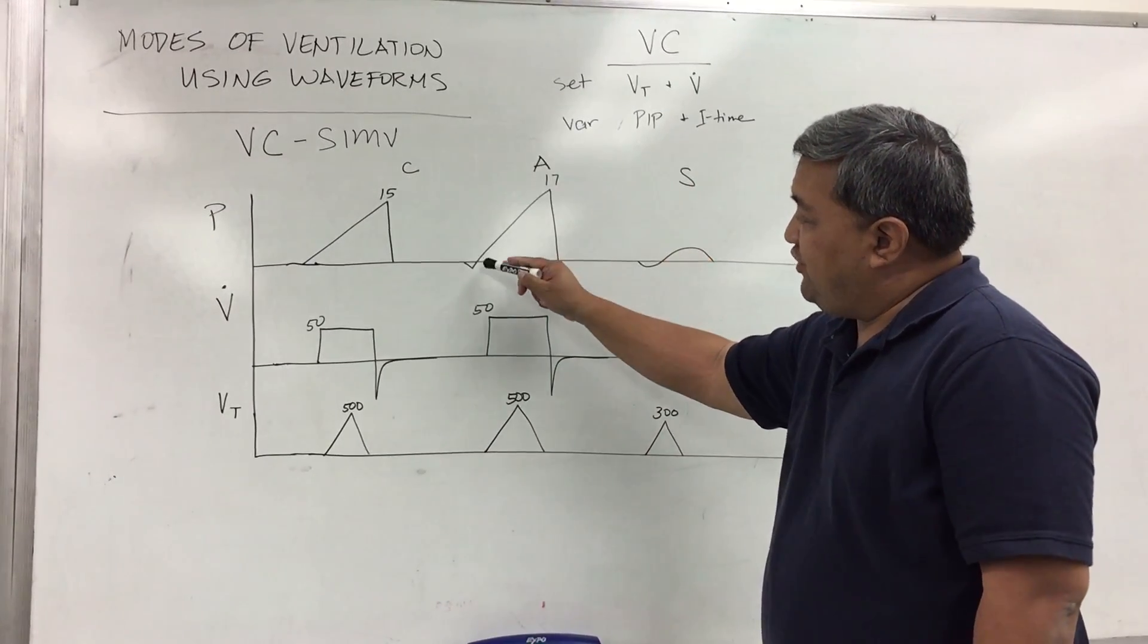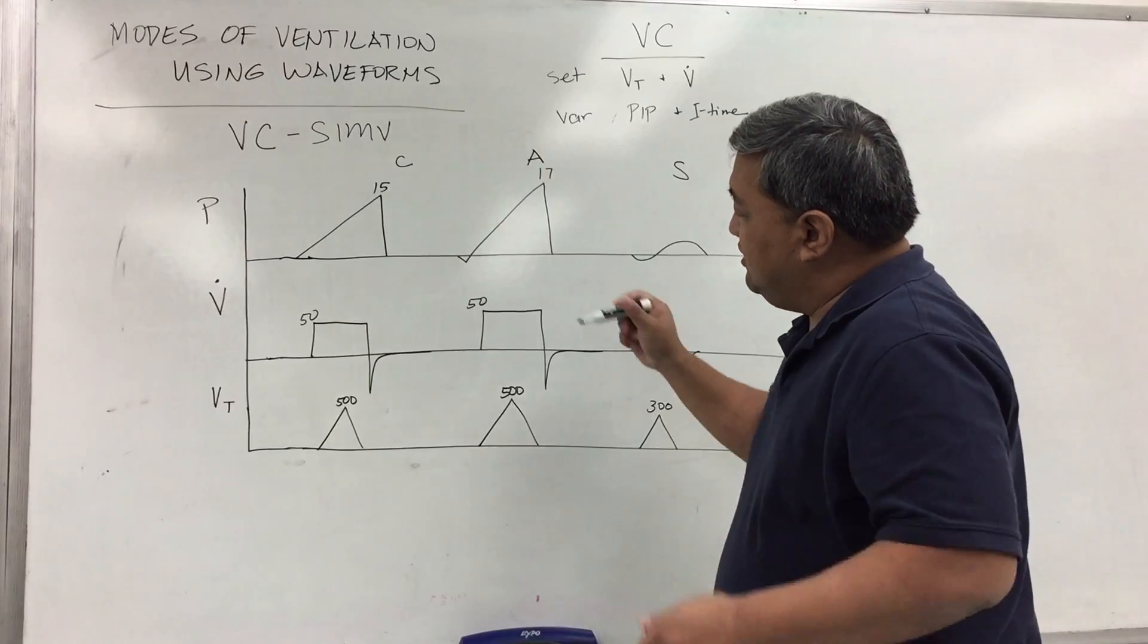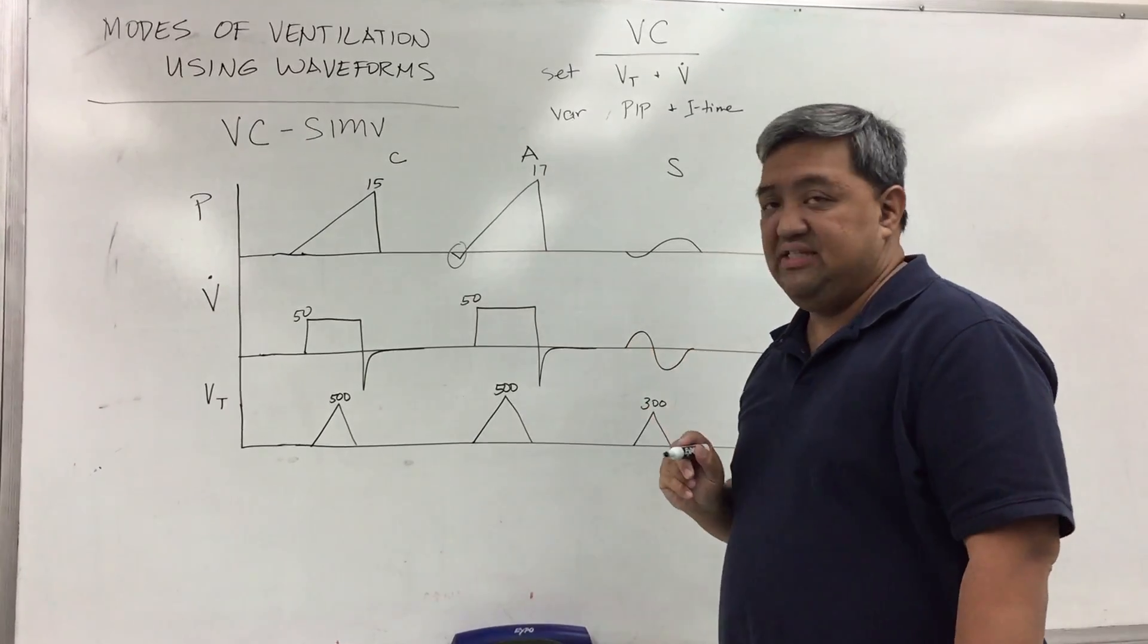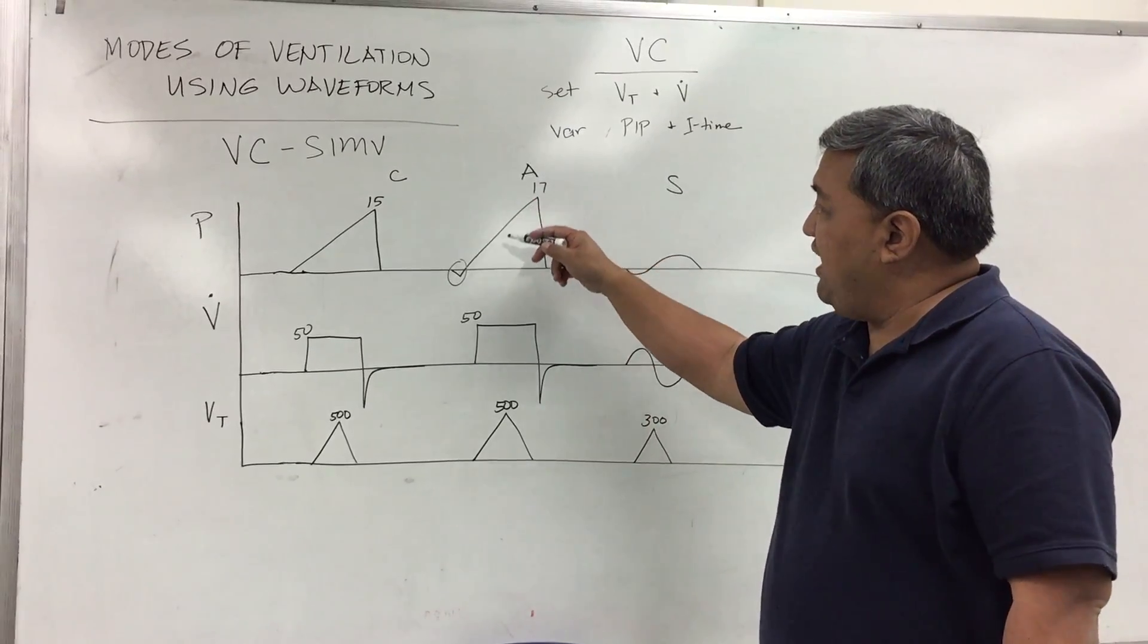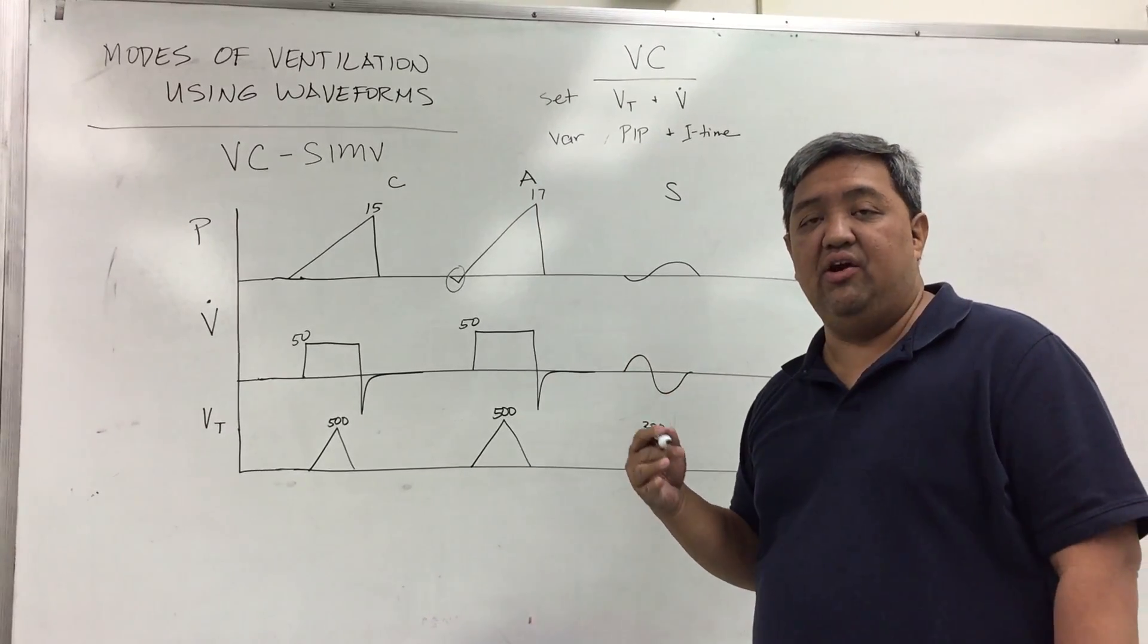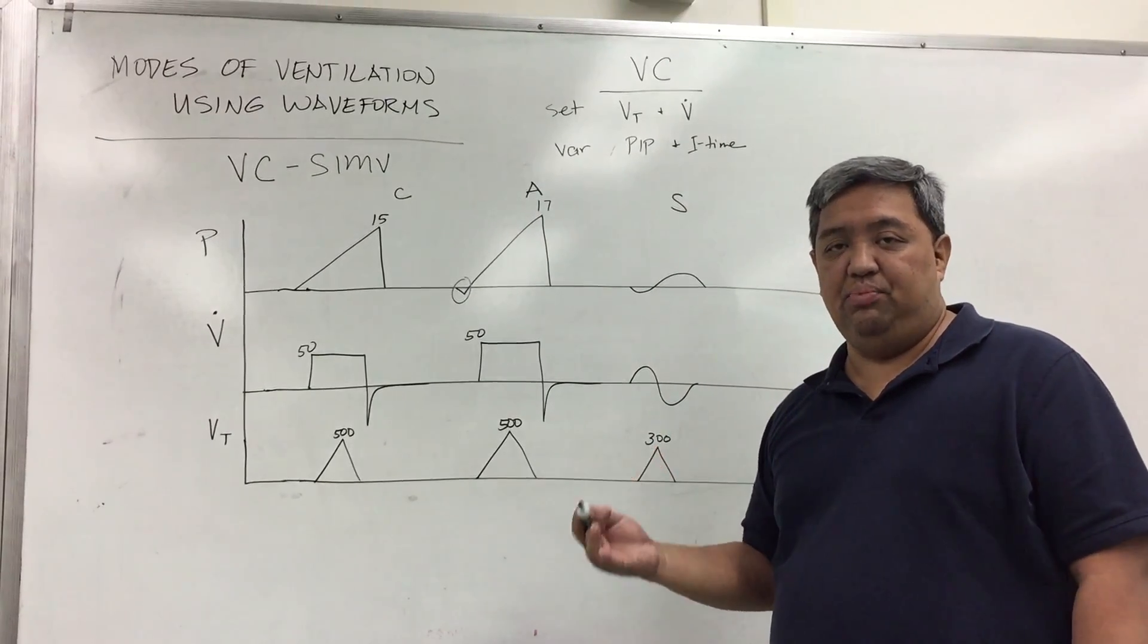On the next breath you have this negative inflection which tells you it is an assisted breath. And again with the same flow and volume you may have a variable pressure depending on the resistance and compliance.